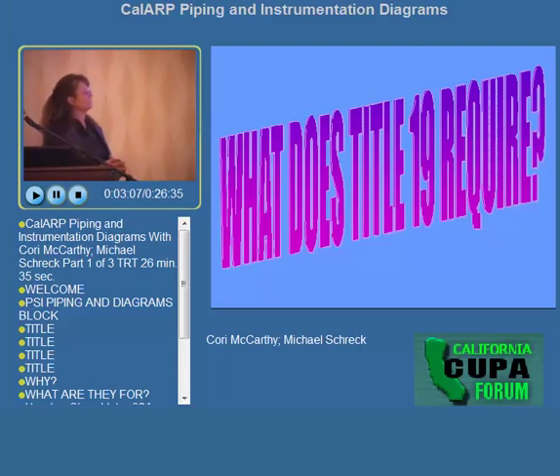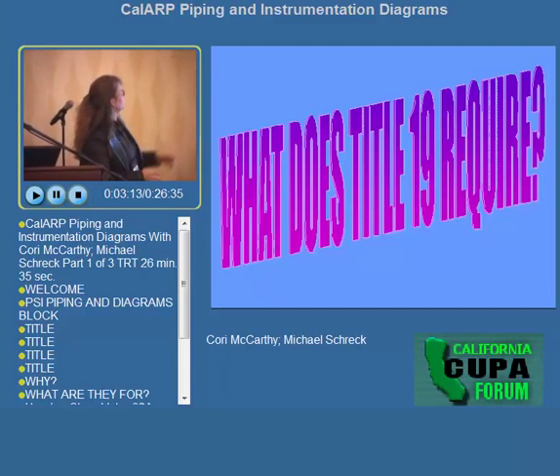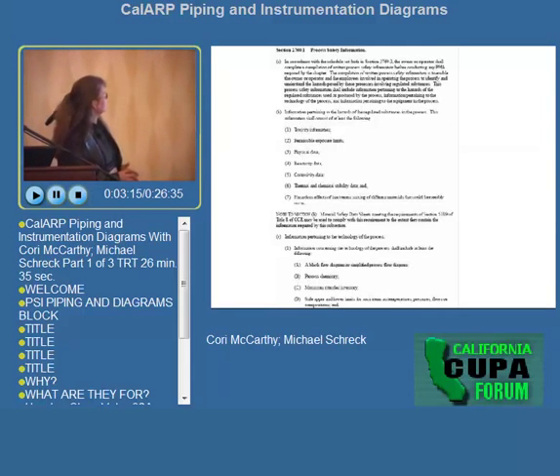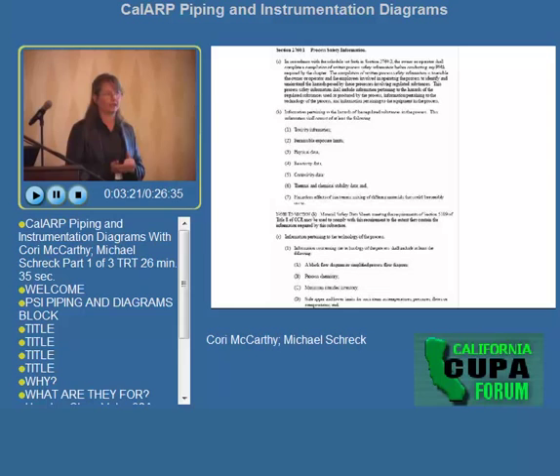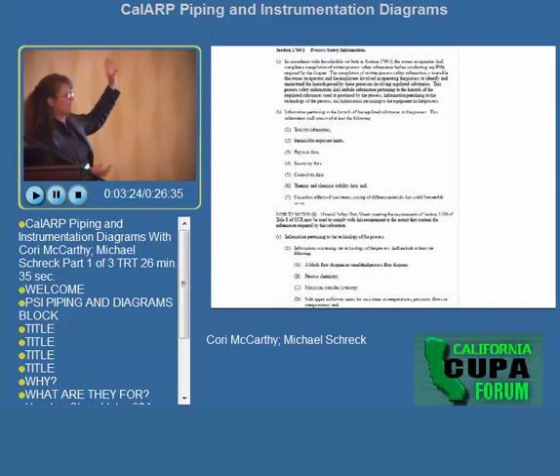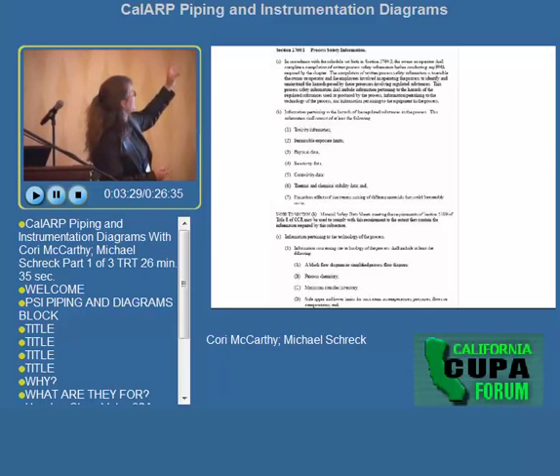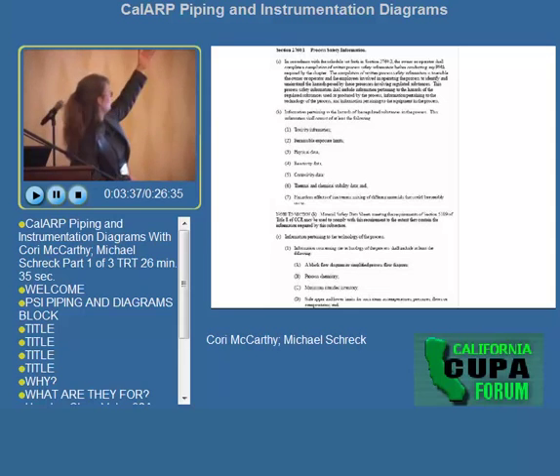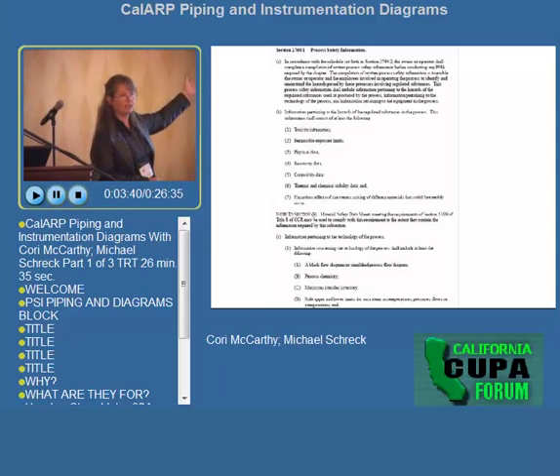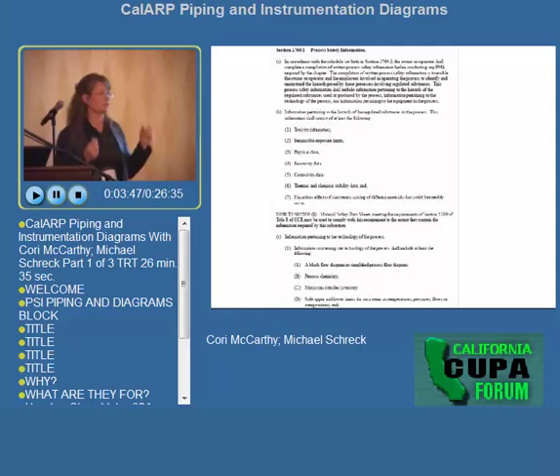So what does Title 19 require for process safety information? From code Section 2760, process safety information, it says that before we conduct a PHA — process hazard analysis — we have to have updated piping and instrumentation diagrams. We also need toxicity information, reactivity, hazards, permissible exposure limits, and corrosivity data. All of these things have to be taken into consideration to have a good and effective process hazard analysis.